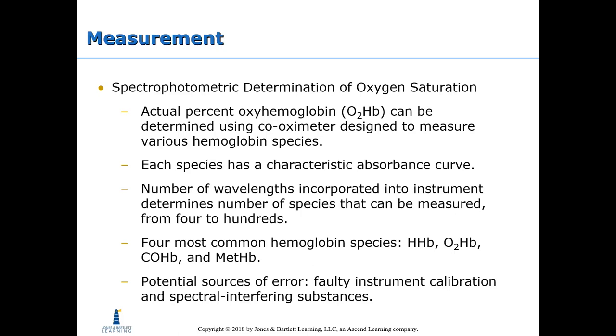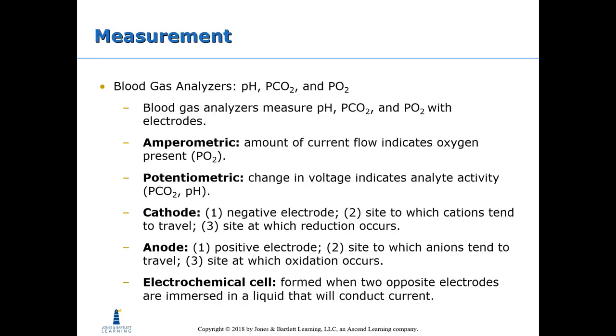Blood gas analyzers measure pH, pCO2, and pO2 with electrodes. Amperometric measurement: the amount of current flow indicates oxygen present. Potentiometric measurement: the change in voltage indicates analyte activity, used for pCO2 and pH. A cathode is the negative electrode — the site to which cations tend to travel and where reduction occurs. An anode is the positive electrode — the site to which anions tend to travel and where oxidation occurs. An electrochemical cell is formed when two opposite electrodes are immersed in a liquid that conducts current.